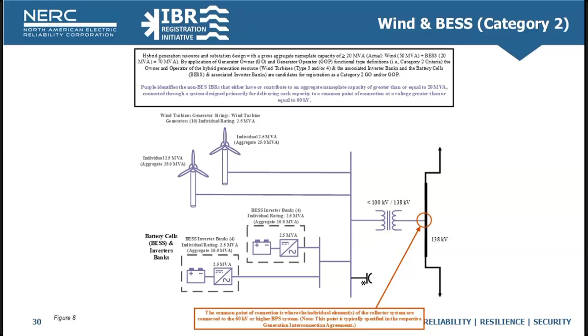So this figure depicts a hybrid generation resource and substation design with multiple owners, identified again as Company A and Company B, consisting of wind and battery energy storage with an aggregate nameplate capacity of greater than or equal to 20 MVA. Similar to the previous example with individual companies owning assets within these facilities, we're going to cover this from a wind and battery energy storage perspective. The hybrid generation resource consists of 6 wind turbine configurations, individually rated at 2.5 MVA, making up the wind component, and 4 inverters, individually rated at 2.5 MVA, making up the battery energy storage component, for an aggregate nameplate capacity of 25 MVA, exceeding the 20 MVA threshold.